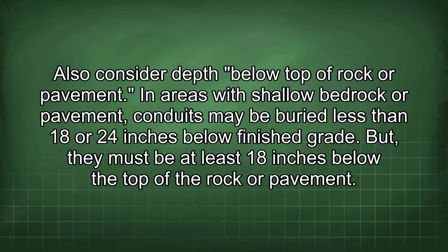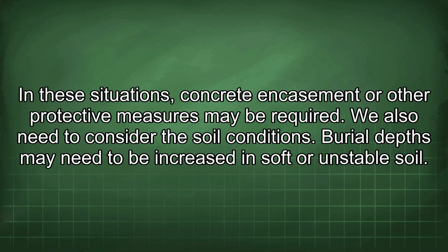Also consider depth below top of rock or pavement. In areas with shallow bedrock or pavement, conduits may be buried less than 18 or 24 inches below finished grade, but they must be at least 18 inches below the top of the rock or pavement. In these situations, concrete encasement or other protective measures may be required.